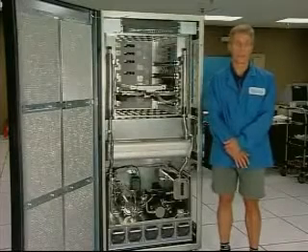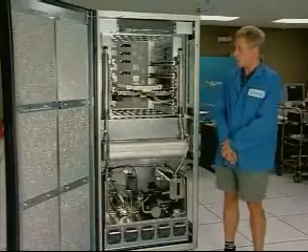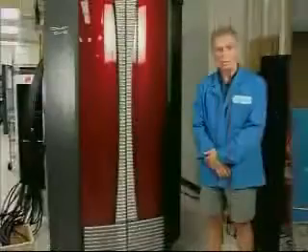This is the SV2 air-cooled chassis, which rejects all the heat generated within the cabinet to the surrounding air. In the air-cooled cabinet, we put in four node modules. If we have more than one cabinet in the system, we'll add two router modules that go up in the top to communicate between the two chassis.